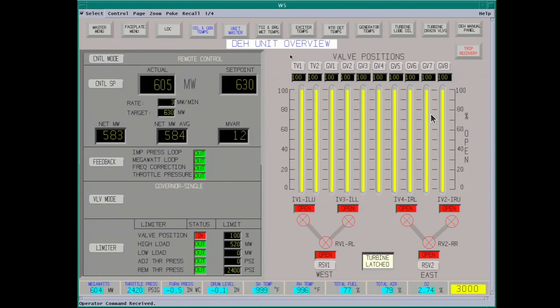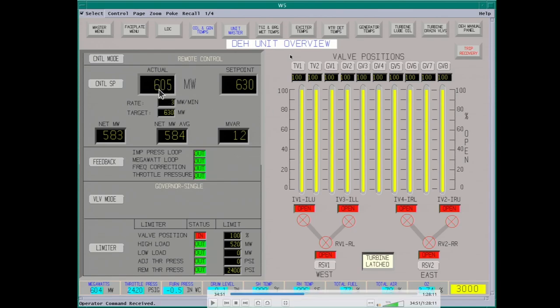There's a lot involved with temperatures and how quickly things are heating up — a lot of thick metal so temperatures are really critical. Net megawatt output is 605 and we're putting out 583. We have 12 megavars plus. You can use your voltage control to adjust the vars. You have your intercept valves and two reheat stop valves for the reheat. Every two weeks all these valves are tested to make sure they work correctly — it's really critical with steam turbines to have valves that aren't hanging up.